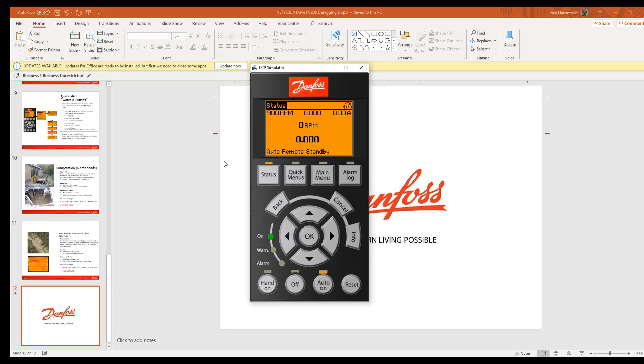Another question came in. Some clients might not realize that they have this feature. If the station is currently clogged, can I come in and just trigger DERAG for a one-time operation? Yes. You can go into the DERAG here and set the cycles that you want to go, and say the function is off here, and I didn't do the power either, but I set up how many cycles, how long I want it to run each direction in this case, what speed, and the off. So I just set those four parameters here, and I just trigger it.